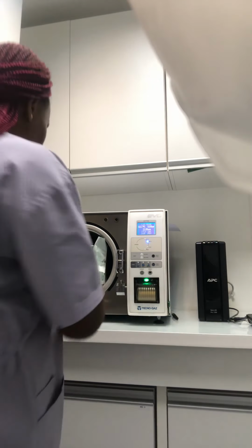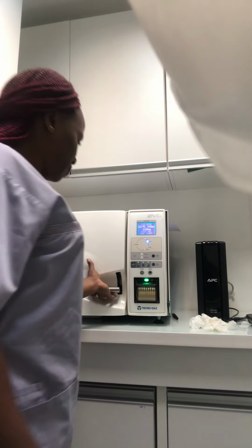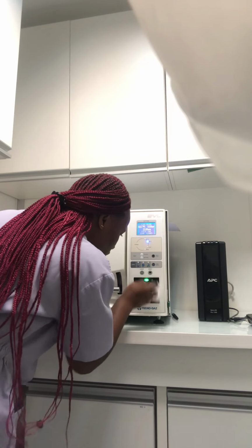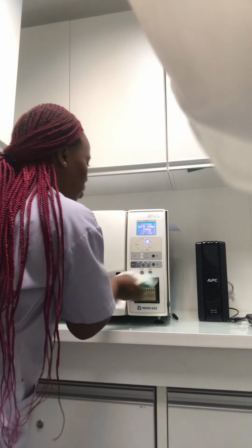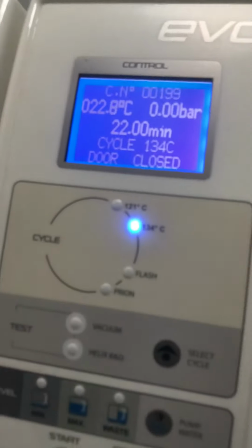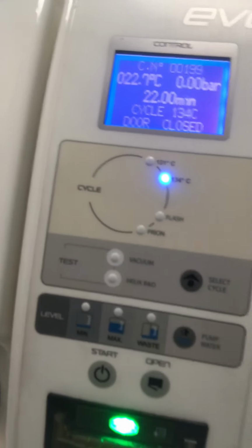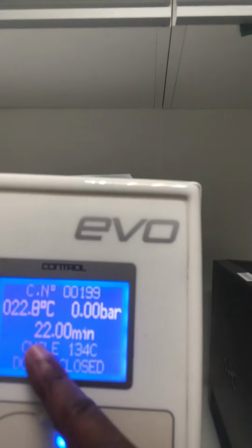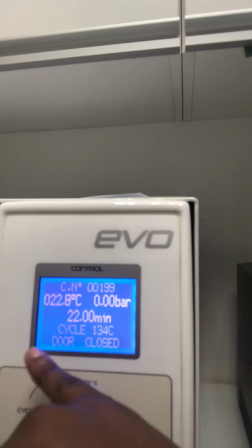So you will close your equipment. Close your equipment. Then if you're sure that you want to start, you're sure that everything is in order, everything has been done, everything has been put in place, make sure you are 100% sure before you start up the equipment, because you don't stop it. Okay, now all the lights have gone. We are to start. So you check all the readings on the screen. The cycle is 134 and the door is closed, so make sure the door is locked, closed, before you start. So I'm sure, and I want to start. Okay.